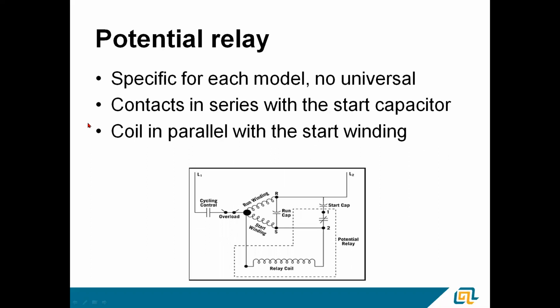Potential relays are specific to each model. There is no universal. It really has to do with the ohm value of the compressor and things of that nature. So if you've got one that's not behaving correctly, you've got to get the correct one. You can't use the universal.